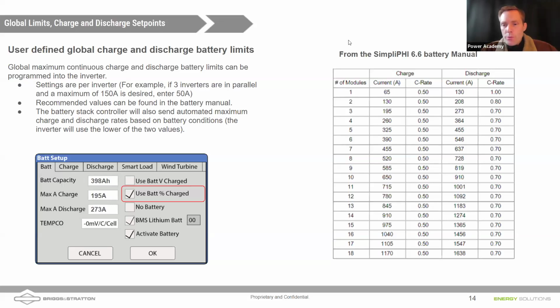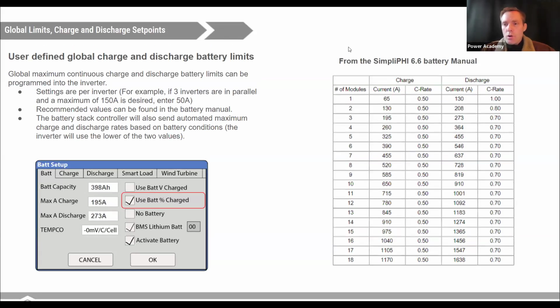So Fred asks, what conditions cause the BMS to shut down, not allowing charging or discharging, and how do you recover batteries functionally in this situation? So one of the things that you would do, Fred, if you do get a fault, let's suppose that your charge controlling equipment was not communicating properly with the battery and was just trying to charge the battery to fault, and that produces a fault on the battery, which opens up the protecting contactor inside the battery.